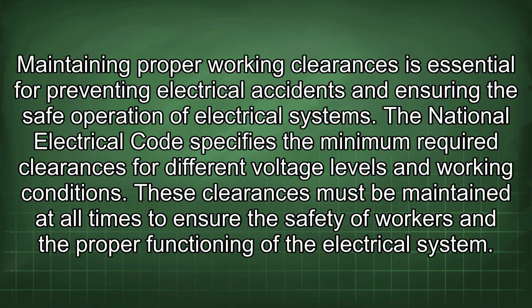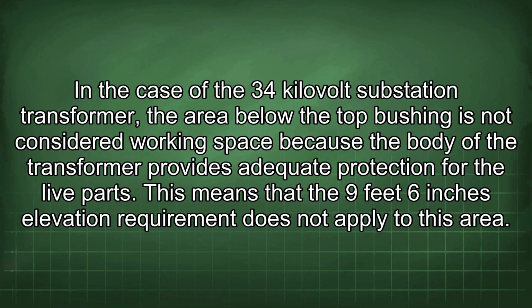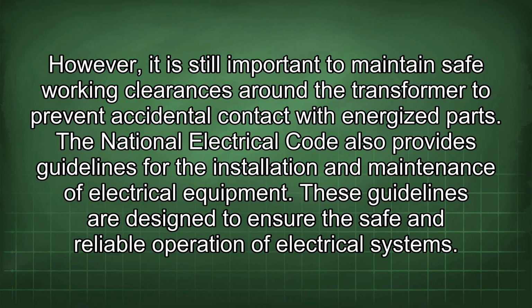The National Electrical Code specifies the minimum required clearances for different voltage levels and working conditions. These clearances must be maintained at all times to ensure the safety of workers and the proper functioning of the electrical system. In the case of the 34 kV substation transformer, the area below the top bushing is not considered working space because the body of the transformer provides adequate protection for the live parts. This means that the 9 feet 6 inches elevation requirement does not apply to this area. However, it is still important to maintain safe working clearances around the transformer to prevent accidental contact with energized parts.